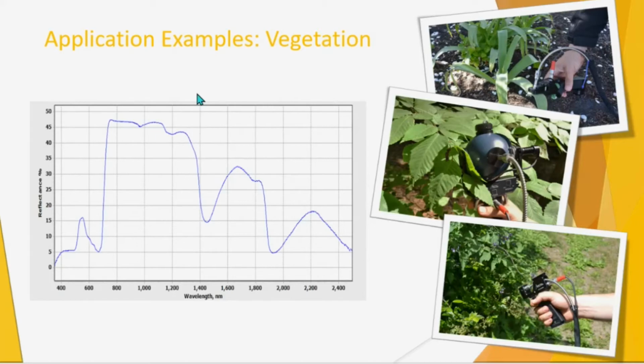On this particular slide, is an example taken with the NaturaSpec of a leaf reflectance sample. So you can see a typical vegetation curve here, going from 350 to 2500 nanometers. To take those samples, I was telling you earlier that we have many different accessories that can be useful. So the base NaturaSpec bundle comes with a fiber optic cable which has a 25-degree field of view.